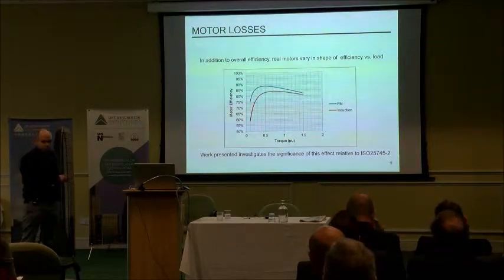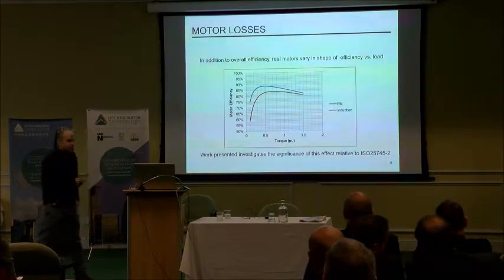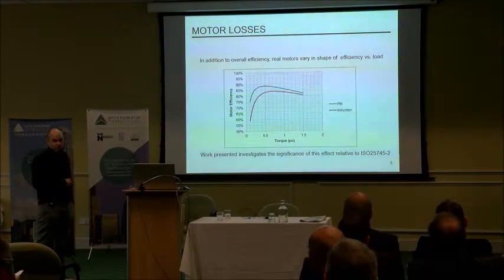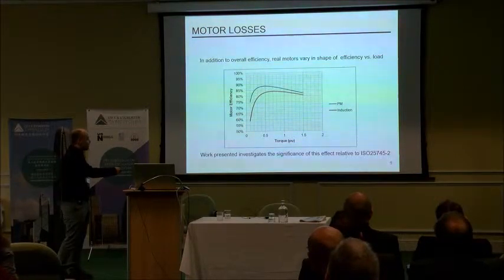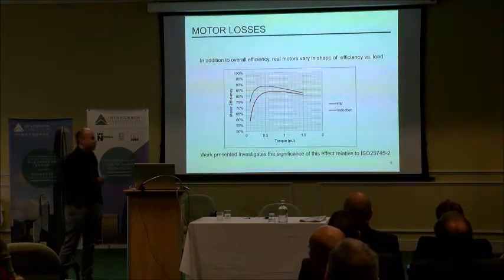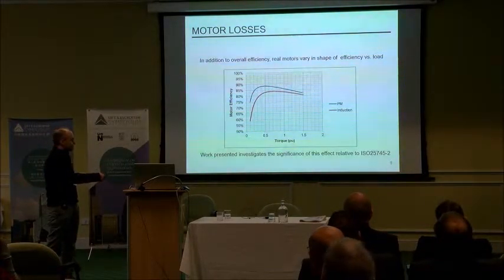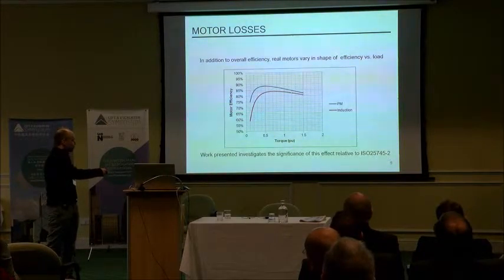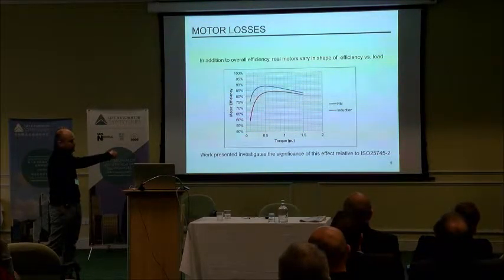As an example, I'll show two motor efficiency plots. We like to talk about motor efficiency as one number, but in reality it's not — a motor's efficiency varies based on its speed and torque. Here I show a PM motor; hypothetically it's 86% efficient at rated torque. As torque goes down, efficiency goes up a little, then at low loads it starts to go down. A similar-sized induction motor is in general less efficient than a PM motor — maybe two points less efficient at full torque. But it's significant to know that that two-point gap increases at low loads. PM motors tend to have a much flatter efficiency curve, while induction motor efficiency falls with load at low loads.